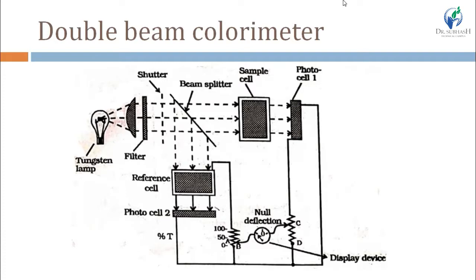This is the double beam colorimeter. The beam splitter splits radiation coming from the filter: part passes through the sample cell and another part passes through the reference cell. Two detectors are displayed — one for the sample cell and one for the reference cell. Other designs use only one detector where beams from sample and reference are combined before reaching the detector.